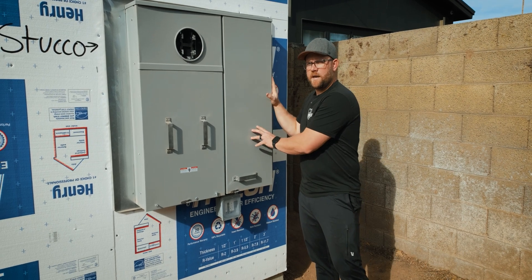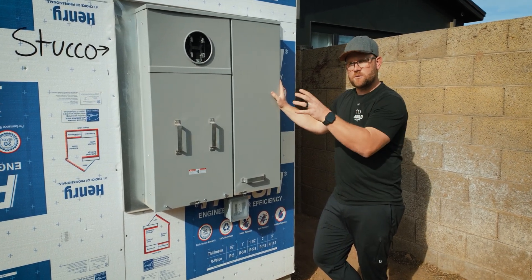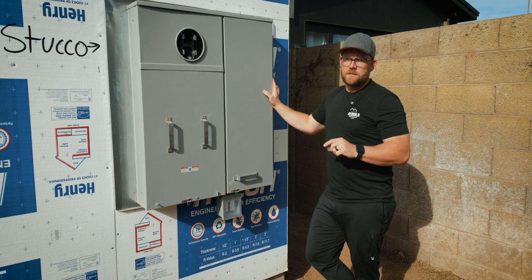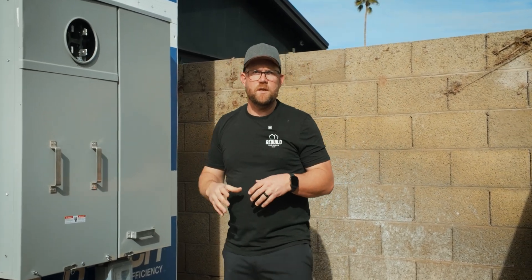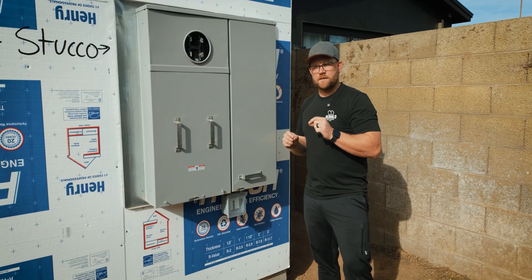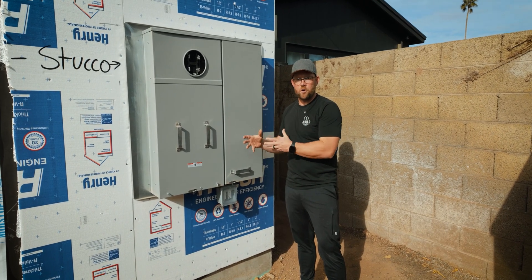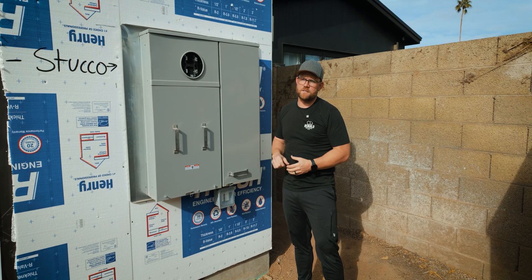Not only do we incur the additional cost of the 400 amp panel to meet the power requirements for dedicated circuits required for modern day living, but we also need an additional sub panel typically placed on the far side of the house for the garage's EV charging station. On top of that, almost every house we build now requires upgrading to a newer transformer, which ultimately costs us and the end user an additional five to seven thousand dollars.